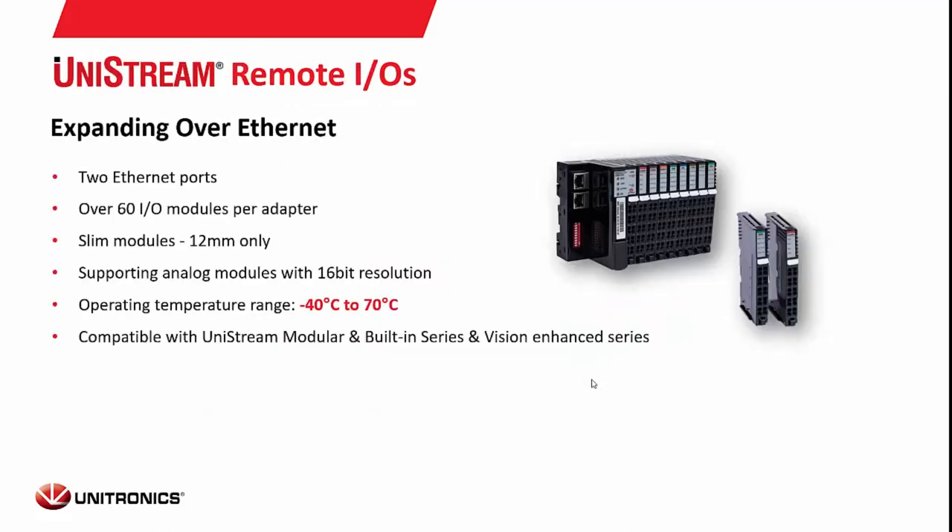We also offer the UniStream remote I/O. Each one has two Ethernet ports and can support over 60 I/O modules per adapter. The modules are very slim, fitting a lot of I/O points into a small area. These are the only systems supporting 16-bit analog resolution and have the widest operating temperature range of all our products. They communicate via Modbus TCP but integrate instantly with the Unilogic software suite, hooking up as if they were I/O modules on the back of your controller.